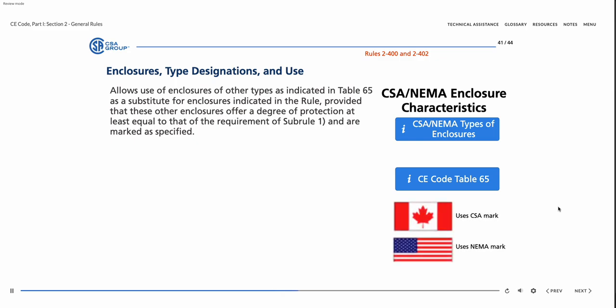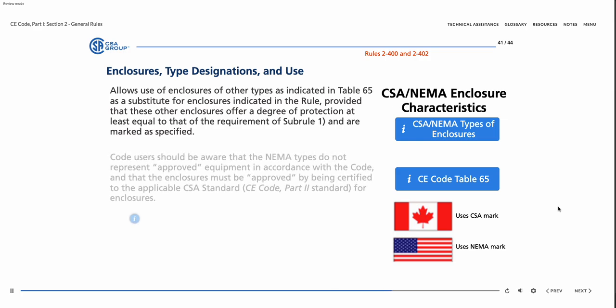The CSA mark for enclosure designations used in Canada is equivalent to the NEMA mark for enclosure designations in the U.S. Occasionally, electrical designers specify an NEMA type for any enclosures. Code users should be aware that the NEMA types do not represent approved equipment in accordance with the code, and that the enclosures must be approved by being certified to the applicable CSA standard, Part 2 standard, for enclosures.